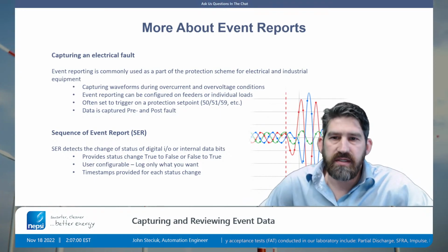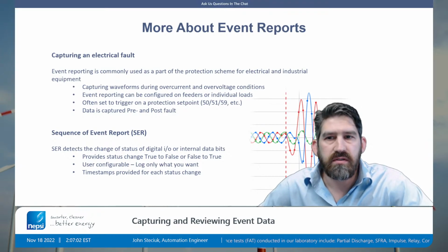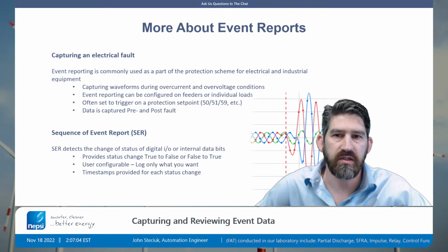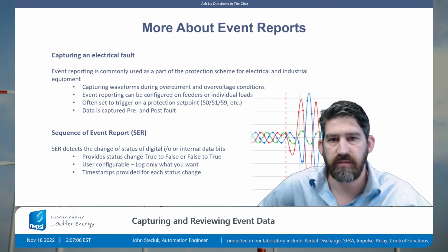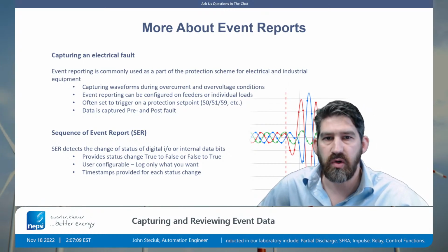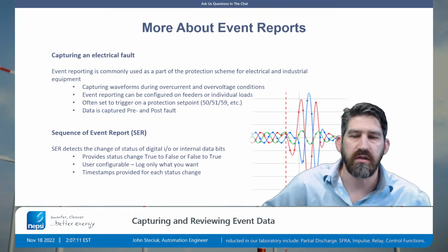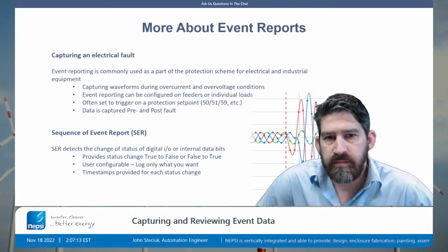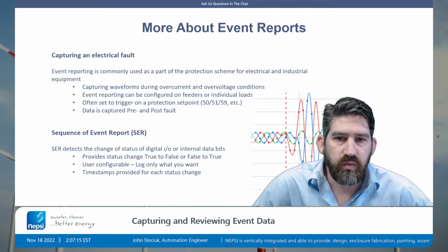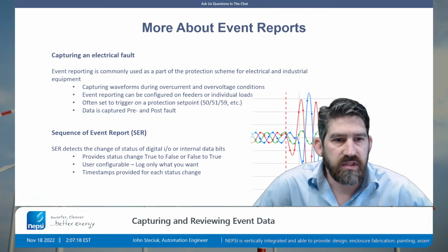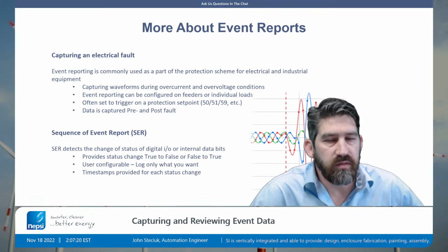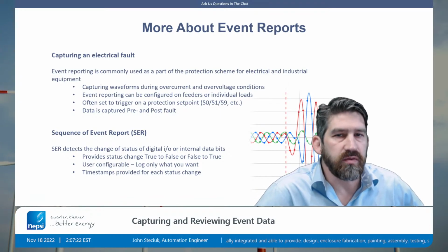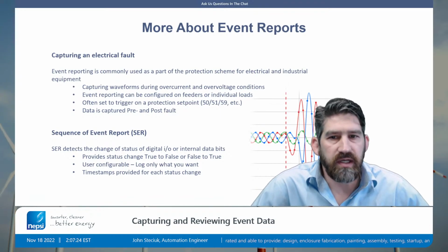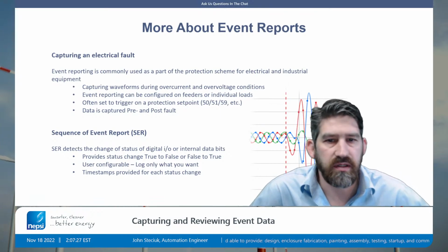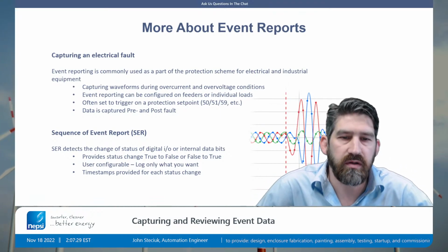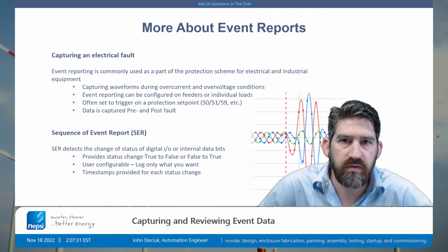Alright, so many times event reporting is used to capture data surrounding an electrical fault. It's used as part of the protection scheme in industrial equipment. So you can capture waveforms during overcurrent and overvoltage conditions. It can be configured on feeders or individual loads.